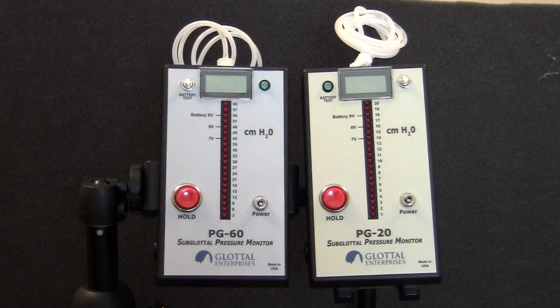However, the PG-20 and PG-60 use an interpolation technique to estimate the subglottal pressure non-invasively from the air pressure in the mouth during a P consonant. The PG-20 and PG-60 are self-contained systems that don't need a computer or computer software for their operation. These two models differ only in the pressure range that is measured. The PG-20 measures up to 20 centimeters of water and covers the range of pressures used for a normal speaking voice, from low to loud.